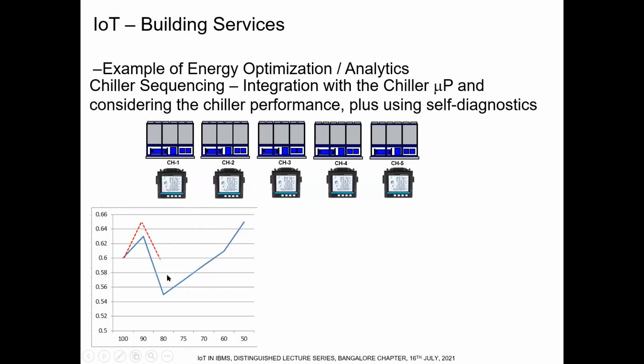So what is happening? Chiller number 4 is actually misbehaving. This is the actual performance characteristic for chiller number 4, where the actual power consumed per ton is much higher than the cataloged value. So what is the inference here? This particular chiller is a rogue chiller, not performing according to what is desired. So the BMS, along with its analytical nature, is recorrecting itself. It is doing a self-study. It is doing online optimization.